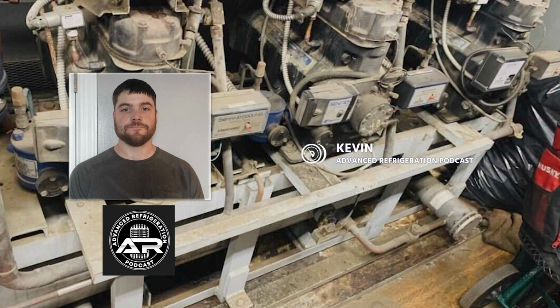whether we're using it to warm up a water heater. So we have a refrigerant heated water heater. It's using the refrigeration heat to heat up the hot water for the store, or it could be using it for air heat, meaning we're heating a coil on a rooftop or an air handler or a unit heater in the back room where we're using the refrigerant heat to reject in the system. So now this becomes even more efficient because now the system's removing heat from the cases, it's refrigerating the cases, and it's taking that heat and using it to heat the store.